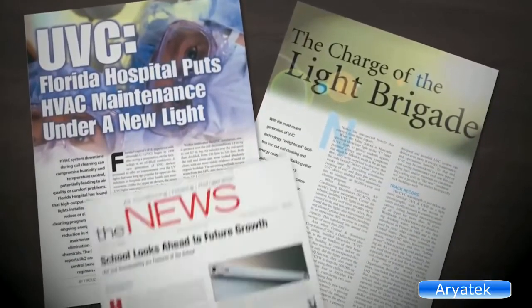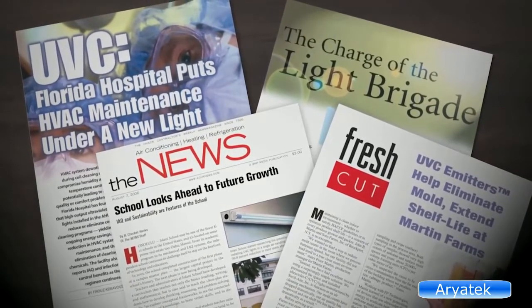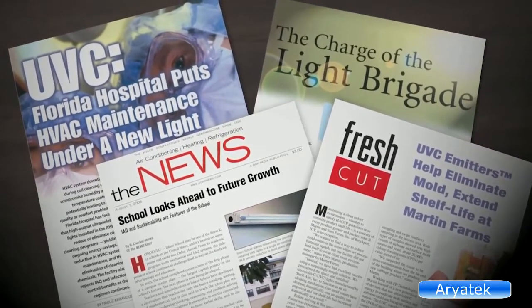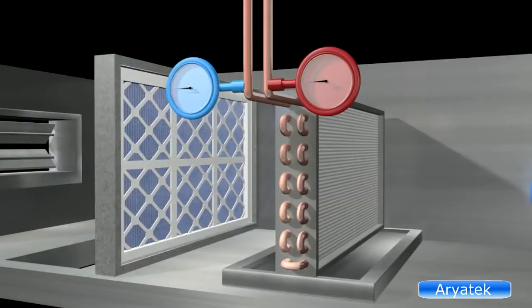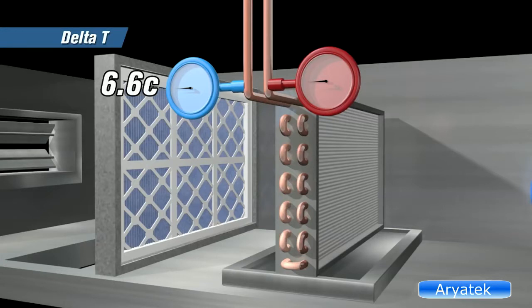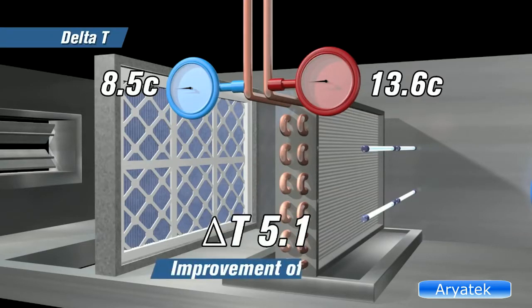SterilAir has numerous examples of energy savings of between 10 and 20%, with payback in 1 to 2 years, and in some cases even faster. The efficiency of the coil can easily be measured by checking the delta T of the coolant entering and leaving the coil. Before SterilAir, the chilled water supply temperature was 6.6 Celsius and the return 9.8, with a delta T of 3.2.